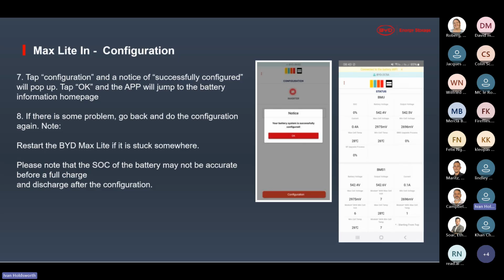So this is a snapshot of someone who wanted to test if they could use the whole battery, and they took their battery from 100% all the way down to 0 SOC, and then the battery turned off on low SOC. To get the batteries to charge again, they just turned the battery on, turned the inverter on, and charged the batteries again. So they were able to use the whole battery. They bought the whole battery. They wanted to use the whole battery. If you do have any issues, it's important to just restart the app and/or battery. And after installation, it's important to maybe cycle the battery once or twice just to get the SOC calibrated.